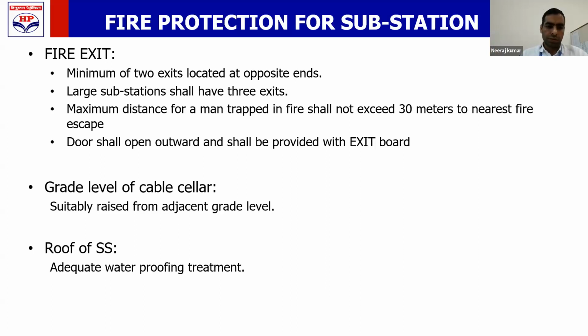Then the roof, how the roof should be constructed. The roof of the substation shall be provided with adequate waterproofing treatment. This has been found significantly important in areas which receive continuous and heavy rainfall. There have been cases where the substation roof had a leak and the water fell on an HT breaker, 11 kV, 33 kV, and in the night the water traveled inside the switchgear and there was a big fire. So to avoid that kind of risk, even though your roof should not leak, to have a secondary protection, waterproofing treatment has to be provided for the roof of the substation.